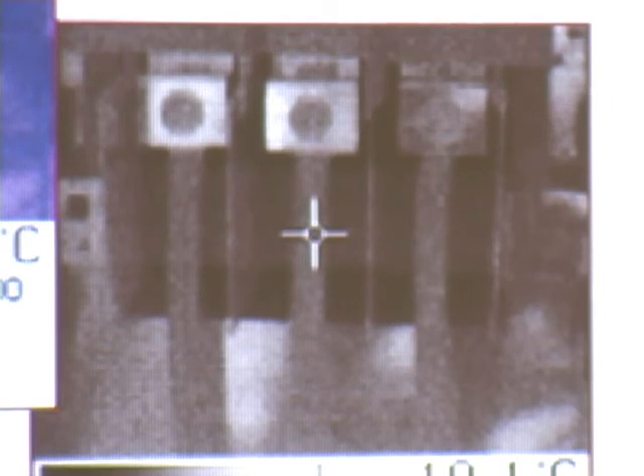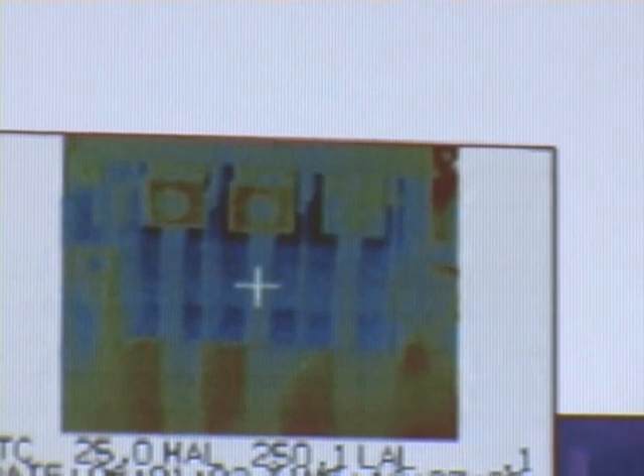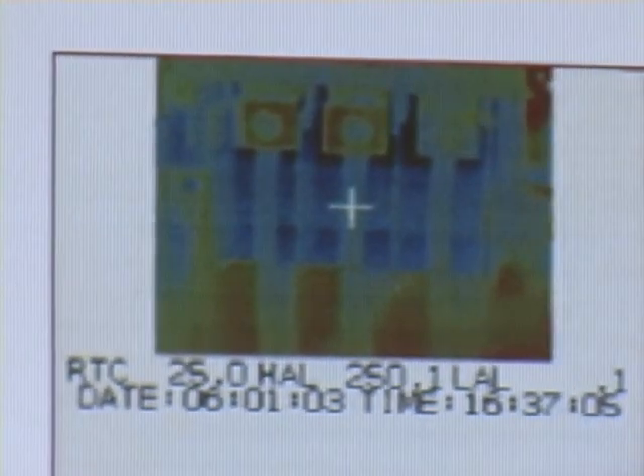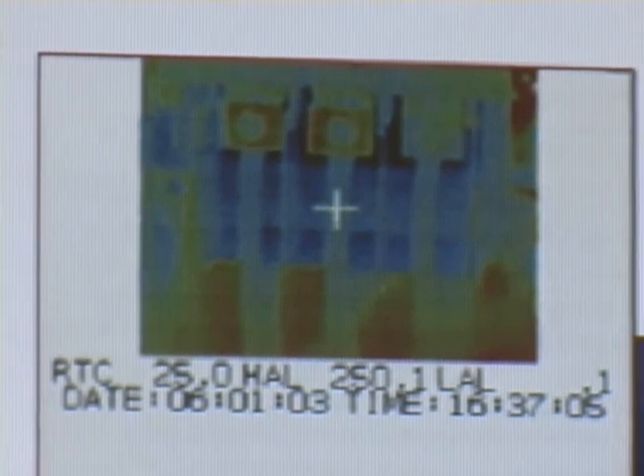Black and white, you're going to find, is by far the easiest to focus. Focusing a thermal camera is very difficult, very challenging. You can go by it in a hurry, especially yours, because it's electronic. Mine's manual, it's easier to control. But you can go by that focus point very easily. It's hard to see. In black and white, it's much easier to see. You get a nice, crisp object. My recommendation: put it in black and white, get your focus, then put it on whatever you want. The ultimate answer to what color you use is personal choice. That's all it is. The black and white one is easier to focus.